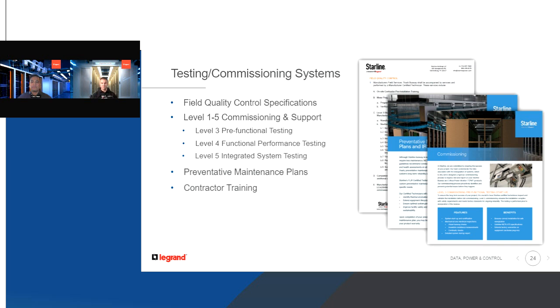That's your level 4 functional performance testing. We really stress that you want to have that in your specification, to do a full load test on that busway, so that day one, when you apply that large load, the busway is installed properly and functional.